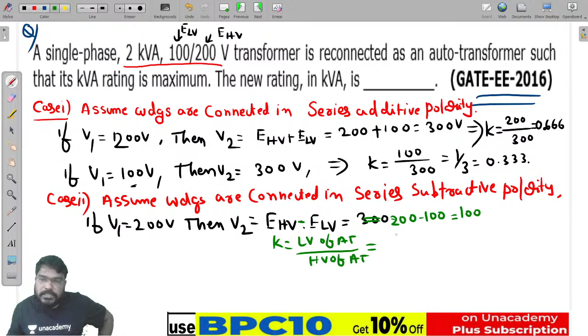EHV minus ELV, 300 minus 200 is equal to 100. Now what about K here? K is equal to low voltage of the auto transformer divided by HV of the auto transformer, so that is 100 divided by 200, which equals 0.5.